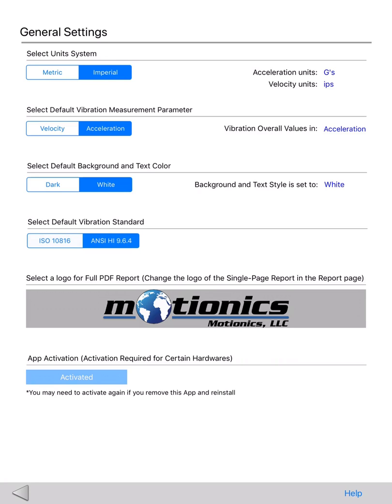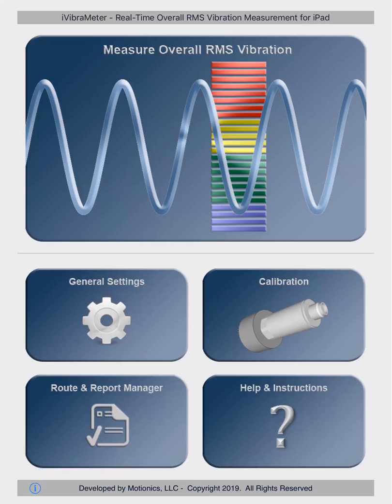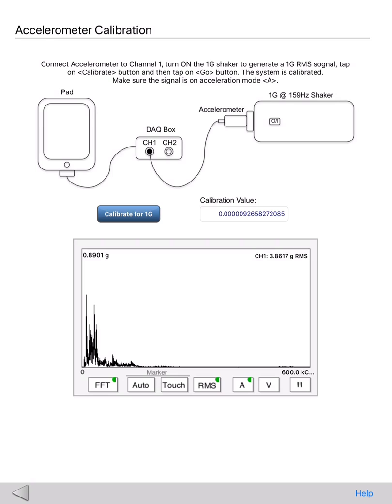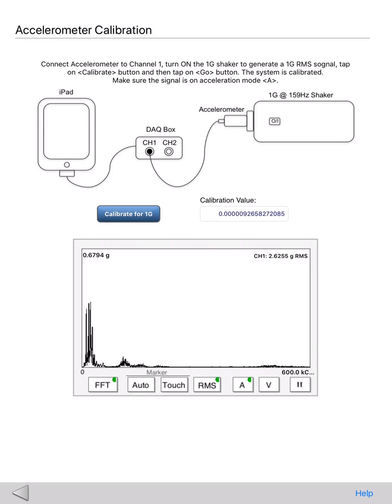Next is a box so you can select a logo for your full report. For the single page report, this can be done in the report page. The last setting is for app activation — you may contact us if the app asks you to activate for certain hardware devices. iVibraMeter has a separate page for easy calibration. If you have a 1G 159Hz shaker, you can connect it to the accelerometer and simply tap a button to calibrate the system. If you don't have a shaker, our hardware device ships with its calibration number and you can enter it here.